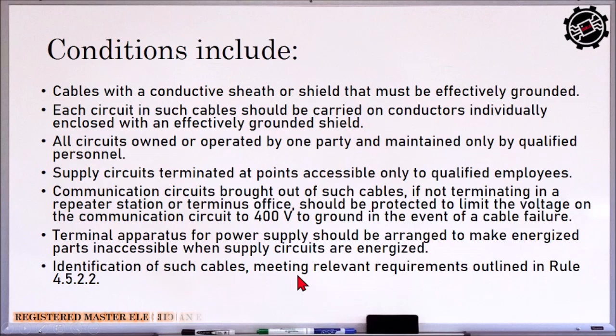Okay. So, parang katulad din yung mga standard kanina. So, direct buried cables of the same circuit operating below 600 volts without an effectively grounded shield or sheath shall be placed in close proximity. So, if the circuit is below 600 volts, tapos wala silang grounded shield or sheath, so they could be placed in close proximity. So, kahit wala na separation. Communication cables containing special circuits supplying power to communication equipment shall be cables with conductive sheath or shield that must be effectively grounded and comply with the requirements of communication cables containing special supply circuits. So, ganun pa rin, no? They must have proper separation, tapos properly grounded.